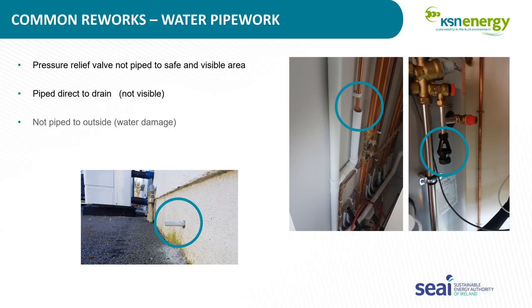You can't always eliminate risk, but what we want is to see the risk being minimized. Where that top one terminates horizontally, if the system overheated, was going up to 100 degrees, pressure built up in the system and it blew off, there's a chance that maybe someone's outside and they might get a burn off of it. Whereas by putting the bend on it, pointing it down towards the ground, it minimizes that. The next one there, where you can see the copper pipe, I've circled it going into the white pipe.